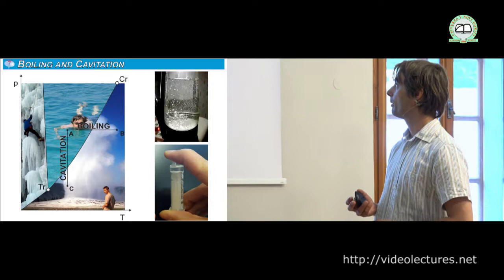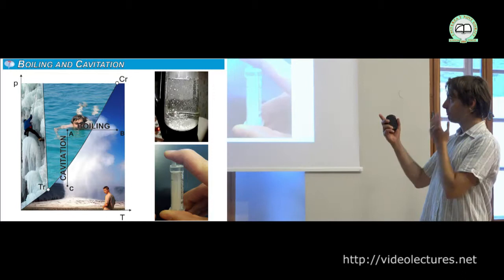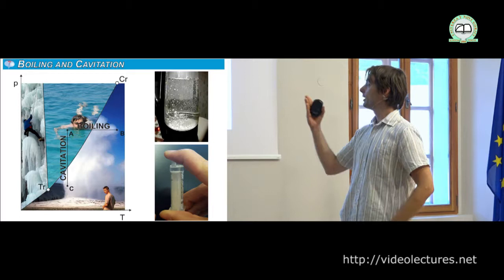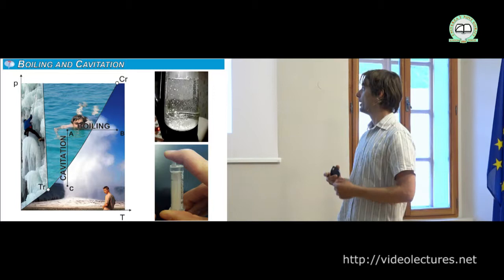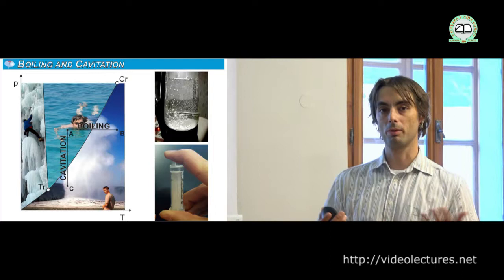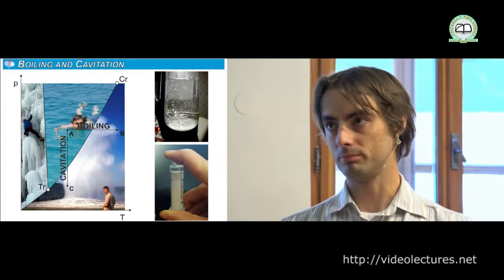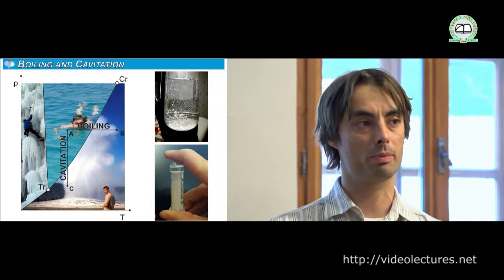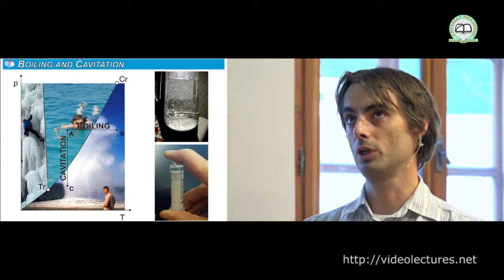I'll start by asking: what is cavitation? Here is a simple diagram showing the three possible states of water — ice, liquid, and vapor. Moving from point A at 20 degrees and one bar, water is liquid. Increasing temperature brings us to boiling at 100 degrees centigrade. But alternatively, you can reach evaporation by lowering the pressure. At 20 degrees, the evaporation pressure is about 0.03 bar — 3,000 pascals — very low pressure.